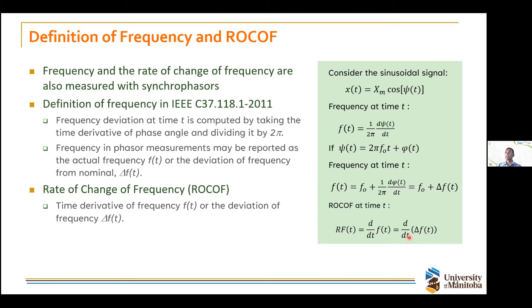So how do you report the synchrophasors? According to the standard, you can report either as real and imaginary parts or as magnitude and phase angle, right? If you're using the phase angle, your angle is reported in the range of minus 180 to plus 180. And of course, the measurements should be reported at one of the standard rates. If it is a 50 Hertz system, you can report at 10, 25, or 50 phasors per second. This is called the frames per second, FPS. If it is a 60 Hertz system, you have more options: 10, 12, 15, 20, 30, or 60. So the idea is that you try to report an integer number of measurements in each complete second.